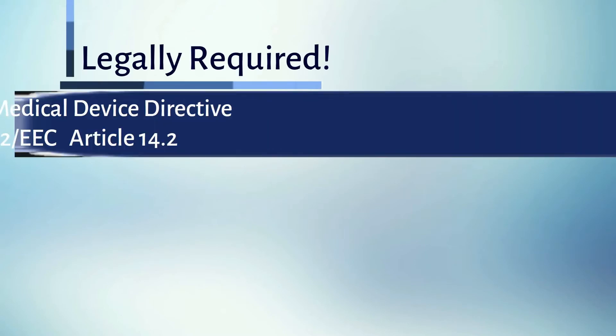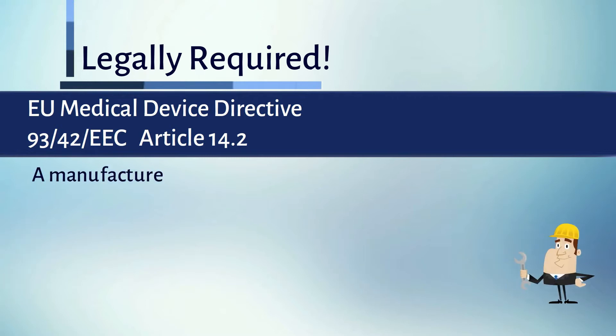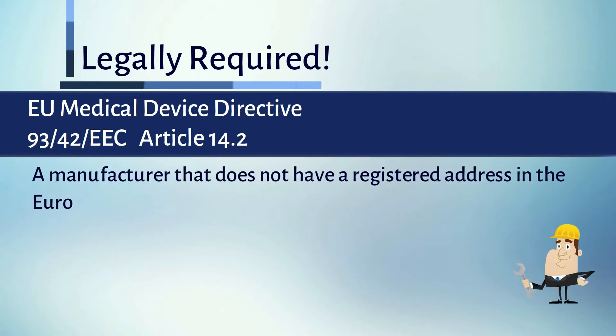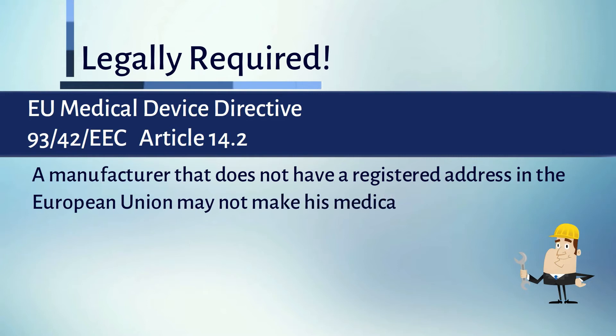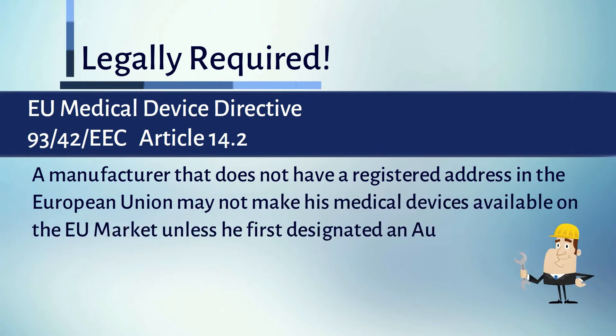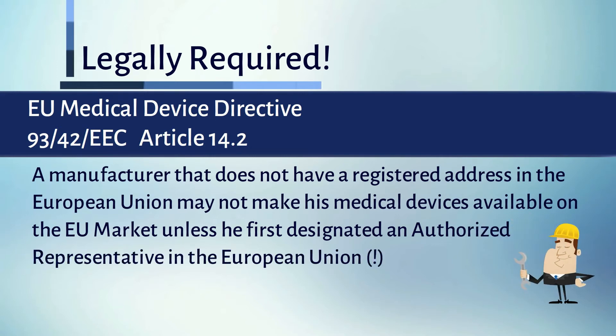The EU Medical Device Directive, Article 14.2 says: A manufacturer that does not have a registered address in the European Union may not make his medical devices available on the EU market unless he first designates an authorized representative in the European Union.